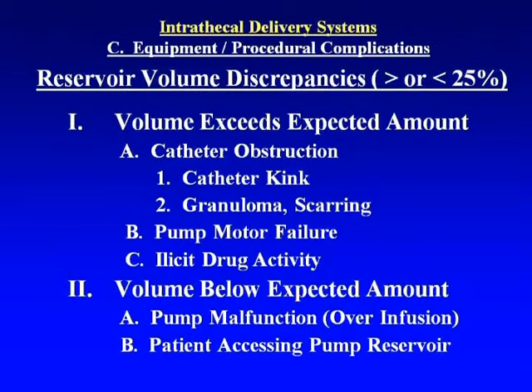It's not a measured volume, it's a calculated volume. So if you have a discrepancy that exceeds the expected amount, you may have catheter obstruction, a granuloma, or scarring at the tip where it doesn't allow it to empty out. You may have pump motor failure, and you might have patients who use the pump illicitly, thinking they can inject illicit drugs into the system to get an effect. This has been reported: people taking drug out and injecting it systemically, or putting drug in thinking it's going into their systemic circulation.